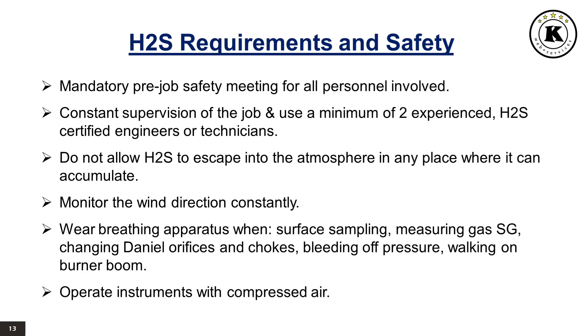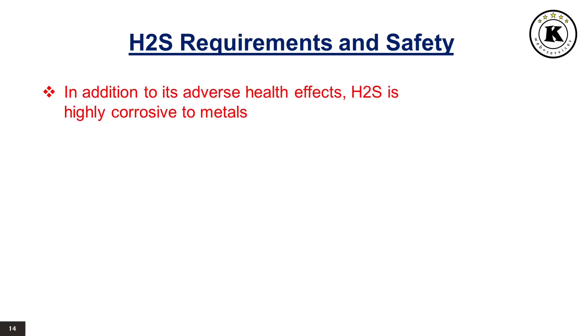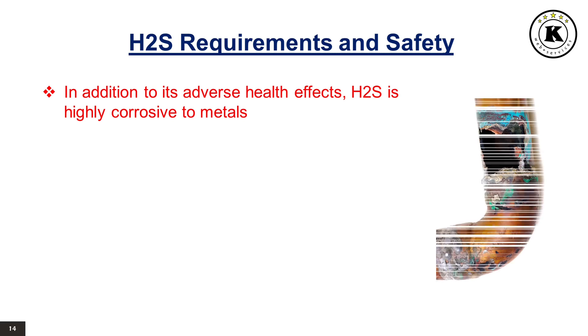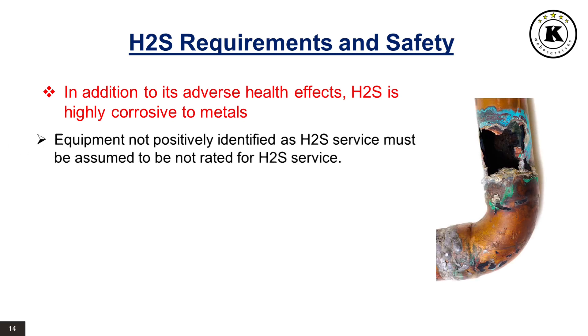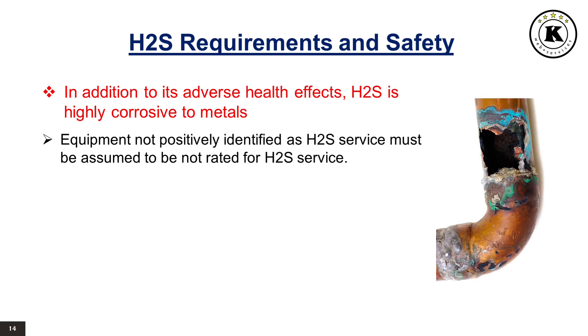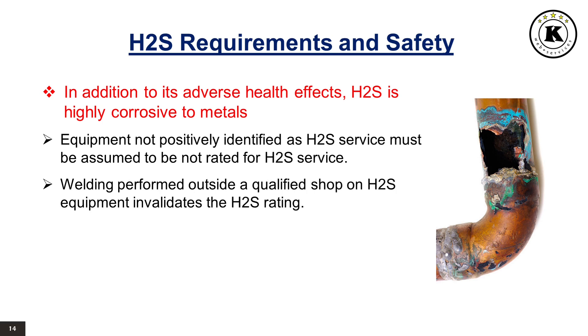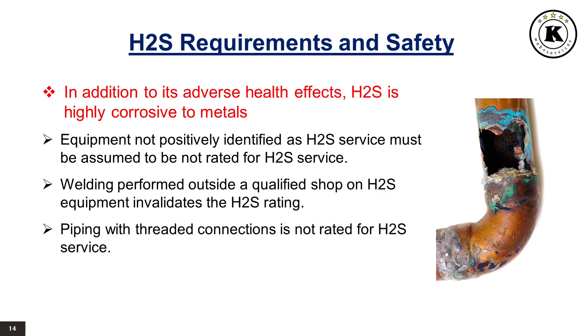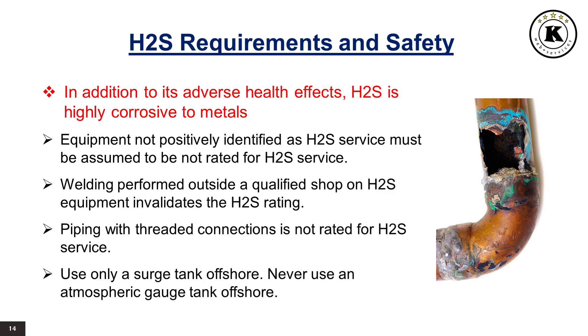Operate instruments with compressed air. In addition to its adverse health effects, H2S is highly corrosive to metals. Equipment not positively identified as H2S service must be assumed to be not rated for H2S service. Welding performed outside a qualified shop on H2S equipment invalidates the H2S rating. Piping with threaded connections is not rated for H2S service. Use only a surge tank offshore — never use an atmospheric gauge tank offshore.